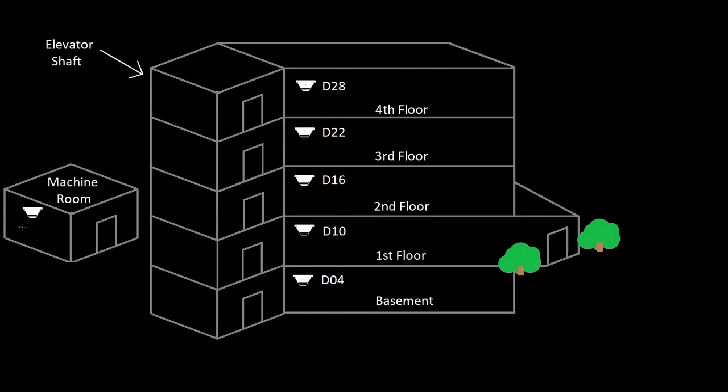Typically when your elevator recalls on either primary or alternate recall, that fireman's hat will come on solid. They want it to flash when there's something wrong with the machine room because with the way that elevator code is, the car will drop down to one in most cases, if the fire is on any floor other than the ground floor. Then the fireman will have the ability to put their key into the door and manually ride it. They need one key in the door and another key in the car itself, and then manually take it to whatever floor they want. That has nothing to do with us, that's all just done on the elevator side. But when something happened in either the machine room, the pit, or the shaft, they want that hat to flash to indicate to the fireman that it's not safe to use the elevator.